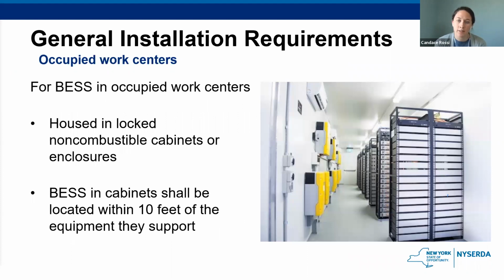Here we have the requirement for systems that are located in occupied work centers. So you need to ensure that they are locked in non-combustible cabinets or enclosures to prevent unauthorized access. Additionally, they must be placed within 10 feet of the equipment they support.